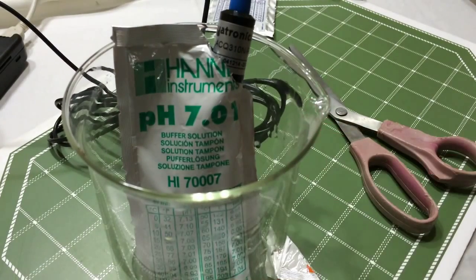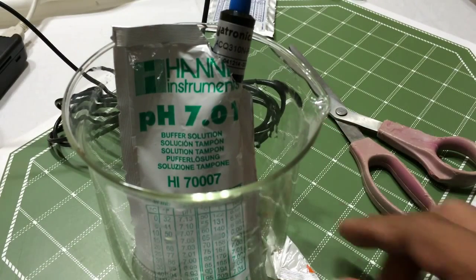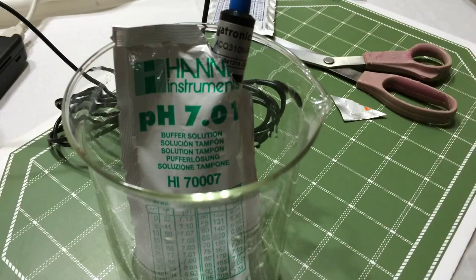And the reason I do that before I even start the calibration is because you want to have it sit in the fluid for a couple minutes to stabilize. So when I start the calibration, it will almost already be stabilized for the 7.01. So I'm going to give this about 5 minutes, and then I'm going to move over and start the calibration.